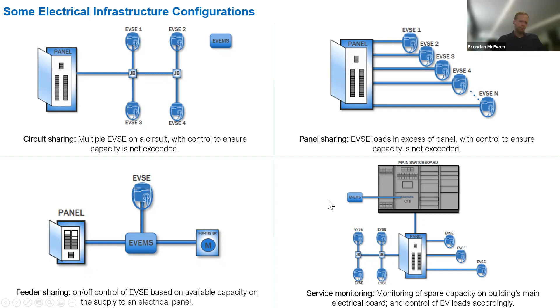It's monitoring how much power is being consumed by the building in real time, then sending signals to your charging stations that it's okay to charge because we're not close to the building's limit, or that you need to throttle back. This lets you take advantage of additional power available in the building. In this diagram, you've got the building load without any EV charging at the bottom, which usually peaks around 6 p.m. in residential buildings, with a lot of capacity remaining in the middle of the night as well as during the day.